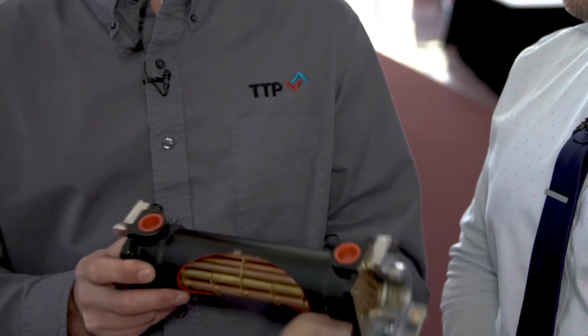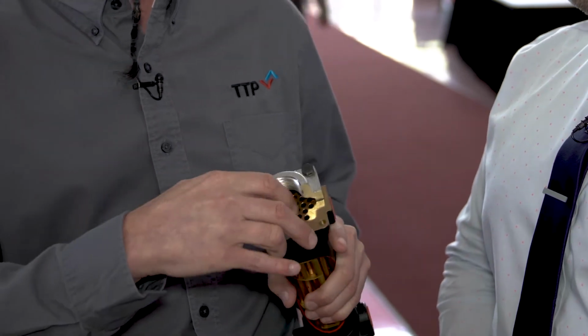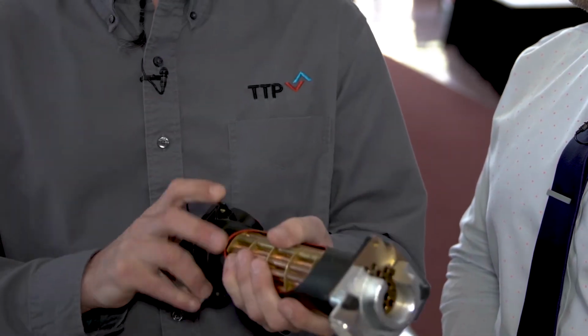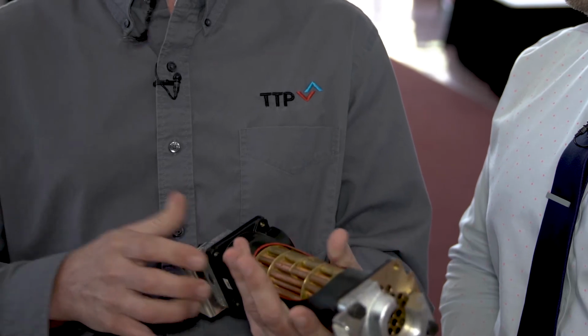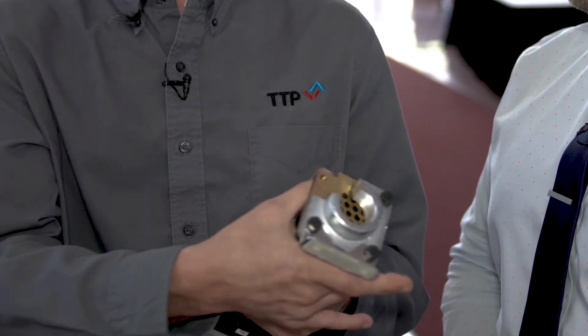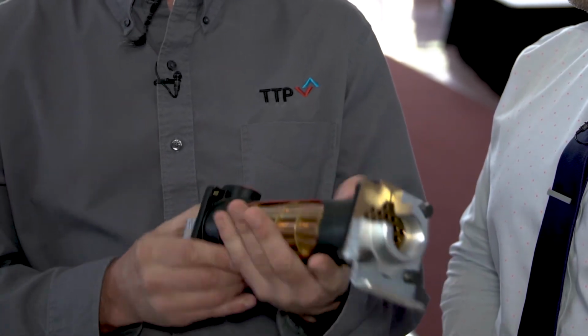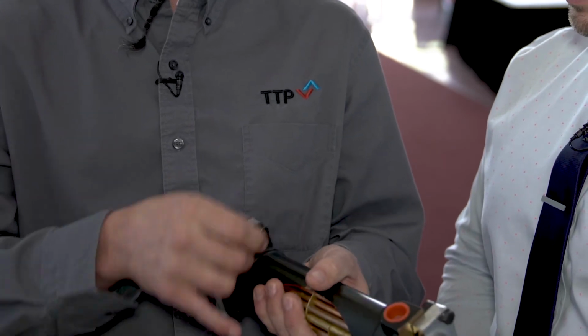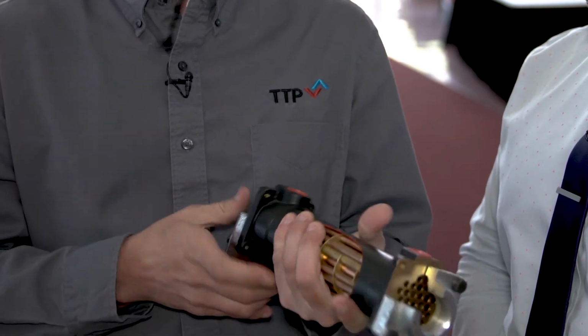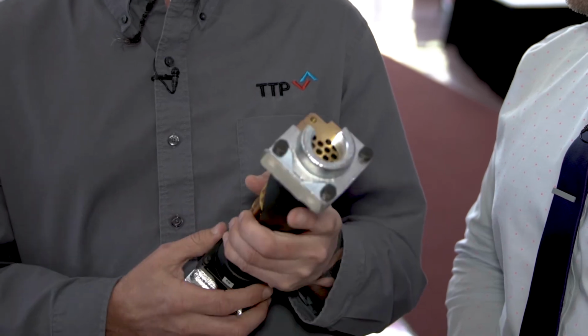The last thing we want to do is make sure that we get enough surface area in the heat exchanger. If you have a heat exchanger that has quarter-inch tubes, you don't want to buy the same shell diameter with 3/8-inch tubes, because you're going to probably lose about 40% of your heat transfer surface area. You can do this a couple of different ways. If you know the shell diameter, you can count the number of tubes on the end. My engineers will know exactly what the tubing diameter is, basically by the quantity of tubes that you can put in a certain diameter. Another way is to look in the top ports. You can figure out exactly what your tubing diameter is. You could probably physically measure it with a caliper.